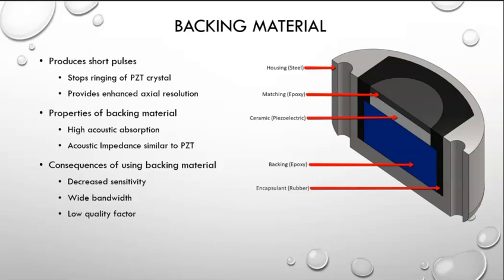All right, let's talk about the backing layer. Without a backing layer, we would have very long pulses. The PZT crystal would just continue to ring when we hit it with a voltage. So the backing layer produces a short pulse, and this is very important for axial resolution and imaging. Some of the properties of the backing material: it is a very high acoustic absorber, so it just absorbs the sound. It has an acoustic impedance very similar to PZT, so that the sound doesn't reflect back into the crystal. The sound easily crosses into the backing layer, and there it's absorbed.